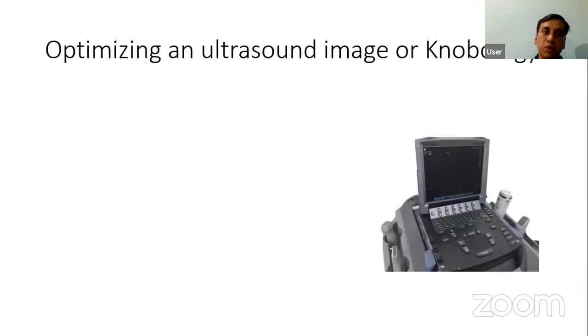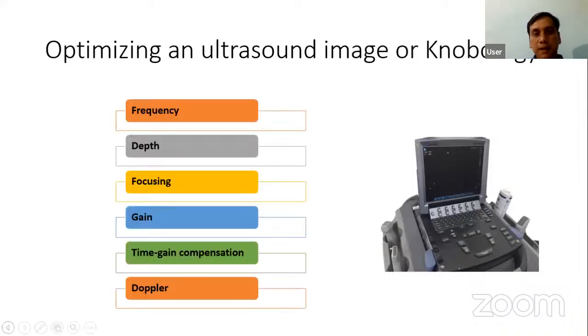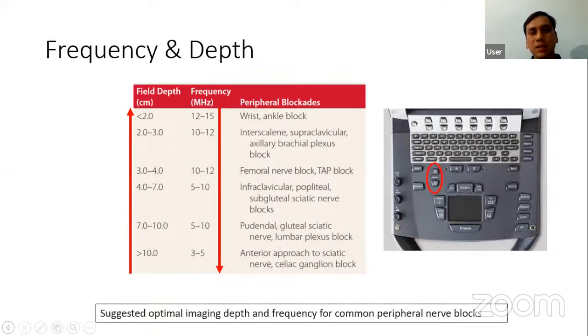Now coming to the most important part, which is how you are going to optimize an ultrasound image. That is, how you are going to use the different knobs of the ultrasound machine to get the best image possible. There are different knobs that you can use to improve the image. There are 6 different knobs: frequency, depth, focusing, gain, and Doppler, that you can use to improve your image. Frequency and depth are the most common ones that we keep toggling to improve our image.